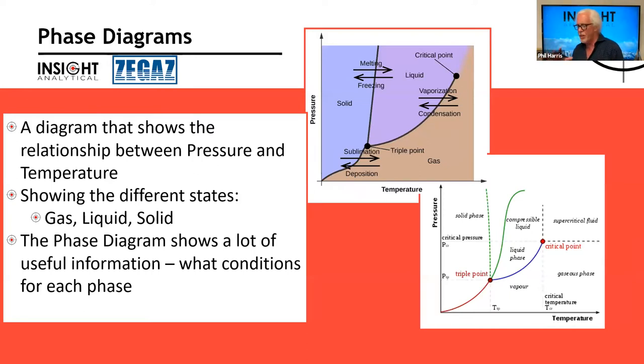If we're going to talk about dew points, it's good to have at least a little bit of an understanding of what a phase diagram looks like. What we're showing on the left over here, on the right, the other left, is a phase diagram for pure water on the top one. What phase diagrams tell us is, if we're at high temperatures and some moderate pressure, we might be over here and everything is a gas on this side. If we cool this down over to here, as soon as we cross this boundary on the phase envelope, it says that it's going to start to condense out and become a liquid.